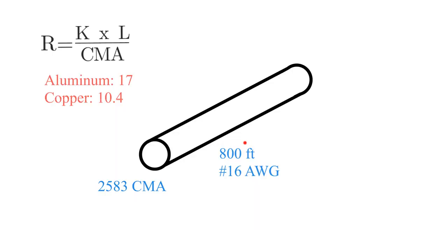So now we have everything we need. We know we have an 800 foot length. We have a number 16, which gives us a CMA of 2,583 CMA. And we know that our copper is 10.4 for resistivity.